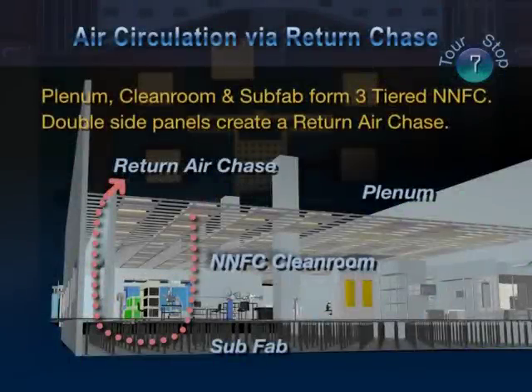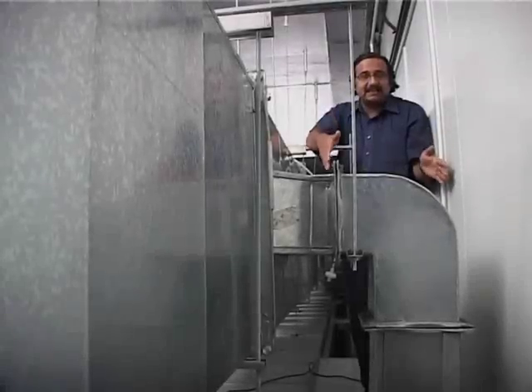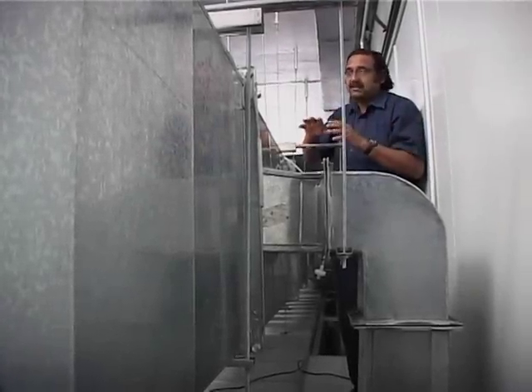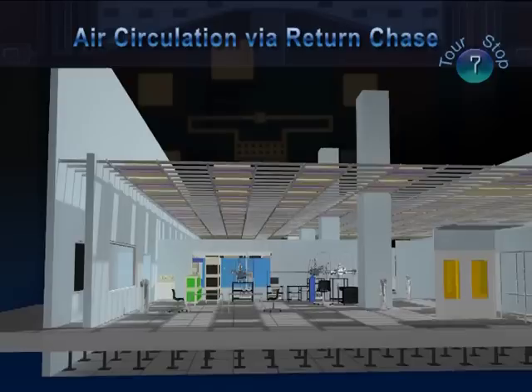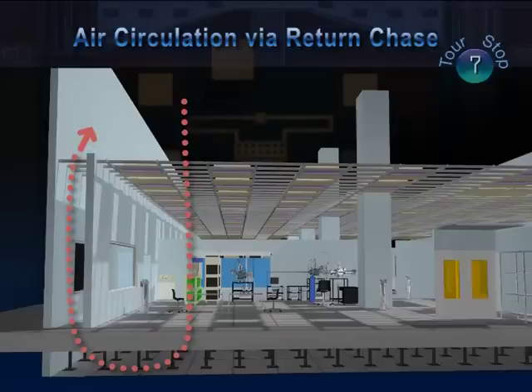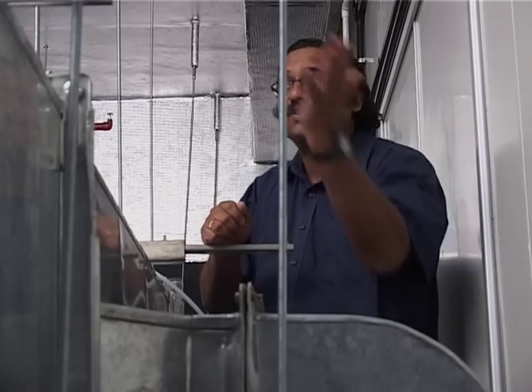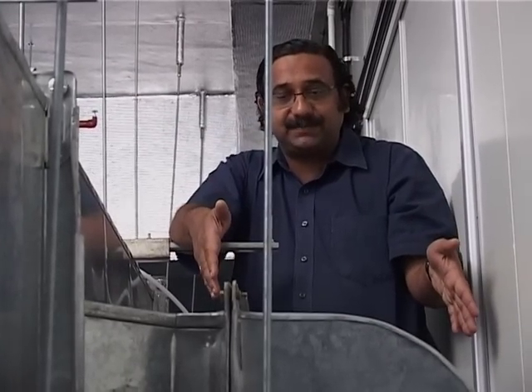The plenum, clean room and subfab form a three-tiered NNFC architecture designed especially for air circulation and other functionalities. The clean room's double side panels create a return air chase for air to flow back to the plenum. This is the return air chase. Earlier we have seen that the air from the plenum area is pushed into the clean room through the fan filter units. This clean air from the clean room gets into the basement of the clean room, or the subfab area, and that air is relatively cleaner than the atmospheric air, so we bring that air back to the plenum area through the return air chase.